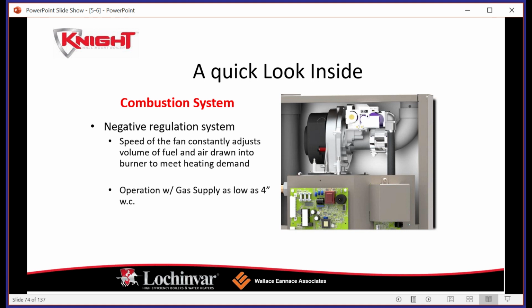So what happens here is that the speed of the fan is going to constantly adjust the volume of the fuel in the air to meet the heating demands. So again, as low as 4 inches water column, that's not what we're shooting for, everybody. We want to shoot for somewhere in the middle. But again, the gas valve is simply going to open, and the gas valve is going to shut once demand is satisfied.